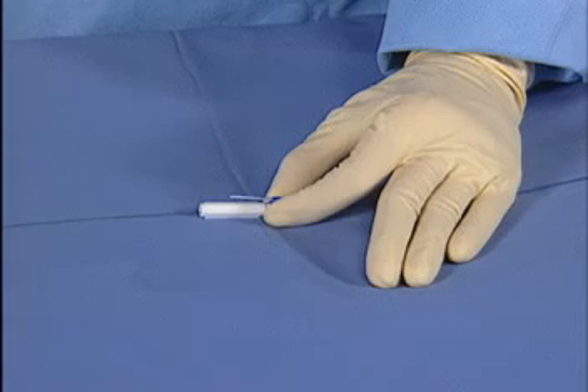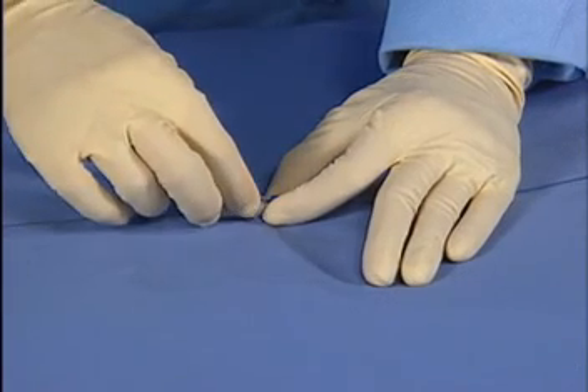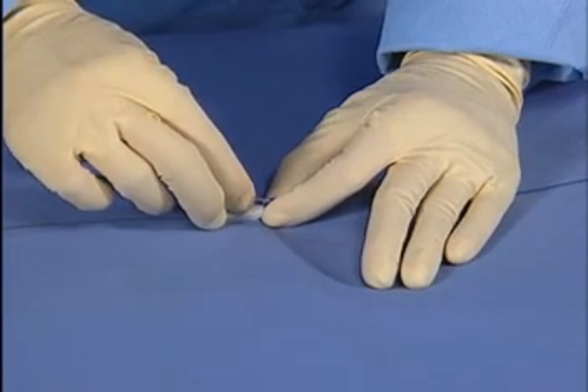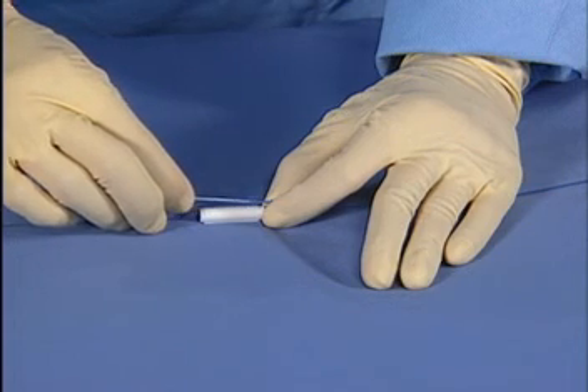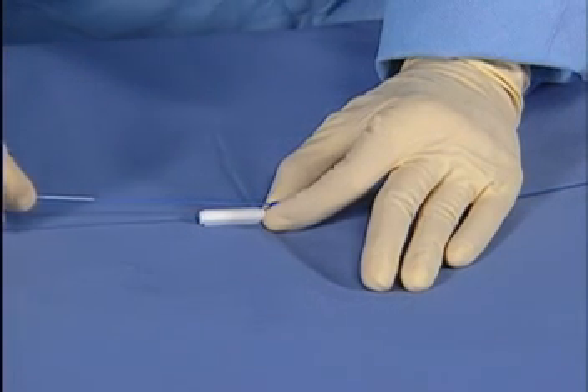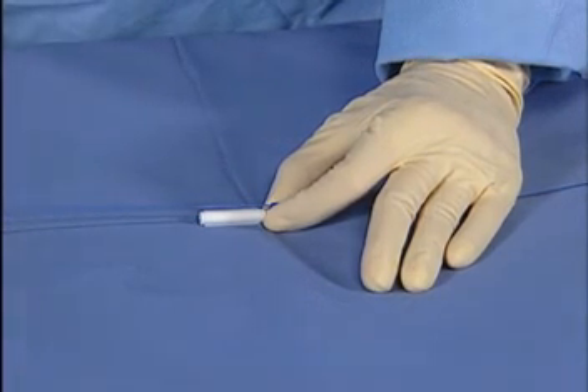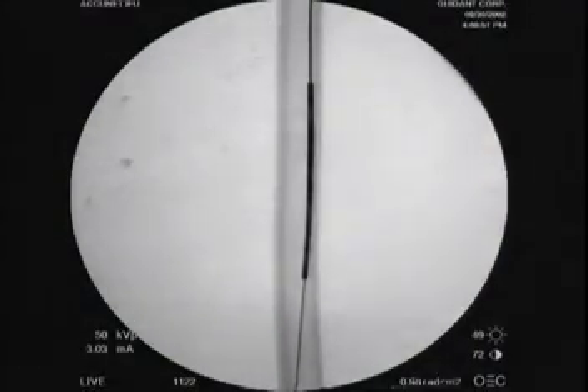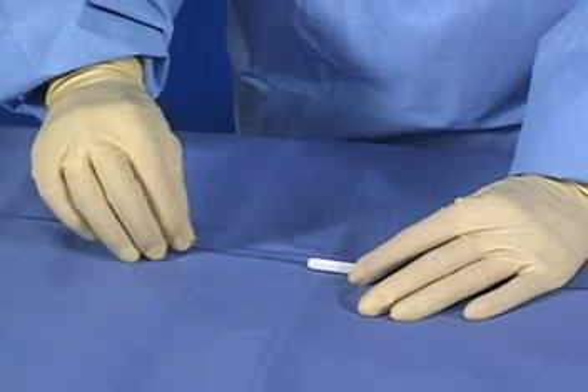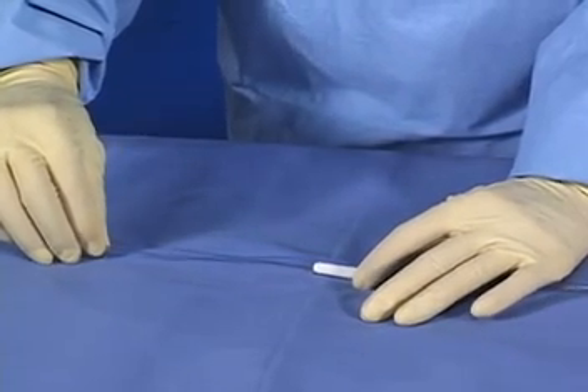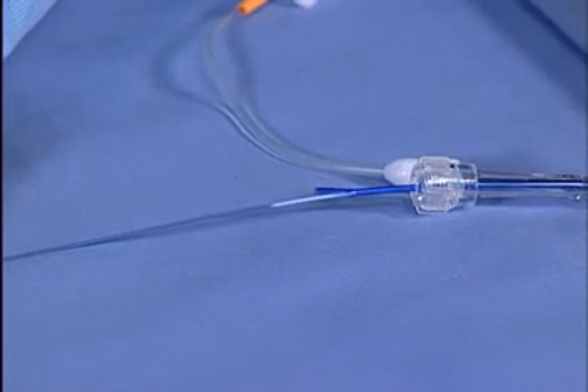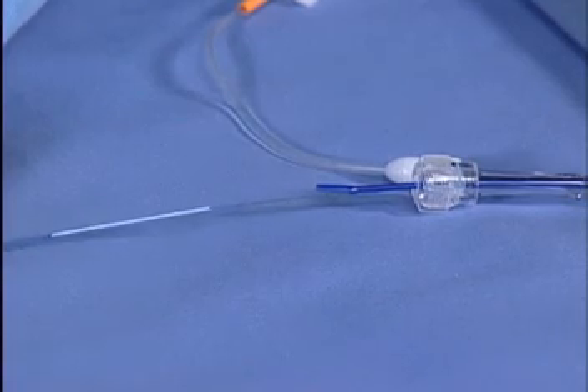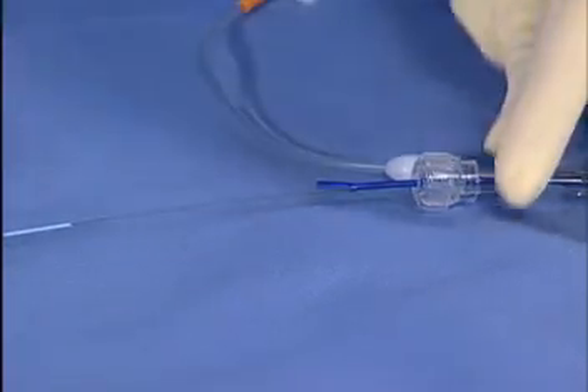With the other hand, grasp the proximal end of the delivery sheath and pull in a horizontal direction away from the patient. This will cause the delivery sheath to peel away at the adapter. Under fluoroscopy, observe the filter basket deployment. Continue to pull horizontally on the delivery sheath until the distal blue section of the sheath exits the hemostasis valve.